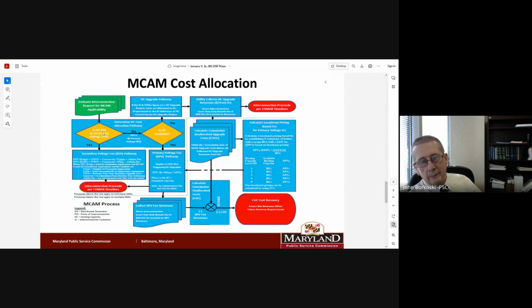The secondary voltage MCAM, we decided we didn't need this complicated method for. What we're basically doing is, anytime there's a secondary voltage upgrade, you have to upgrade transformers, and we're just collecting all that money in a big bucket, resetting the fee for customers every year. So that customer I was talking about before, who got charged $8,000 to upgrade a transformer, in the future the utility would just upgrade the transformer and maybe charge each customer, including that one, maybe $100 or $200.